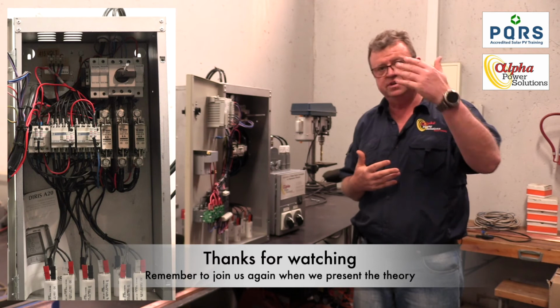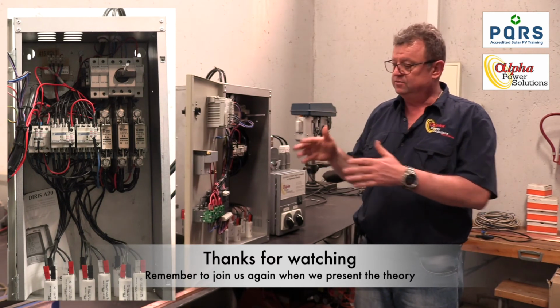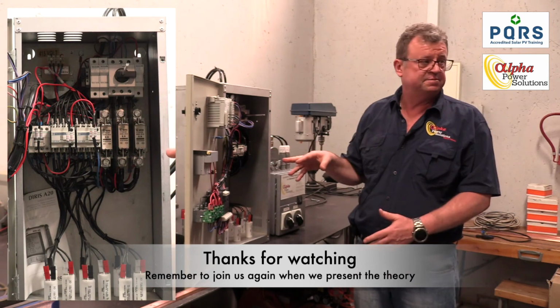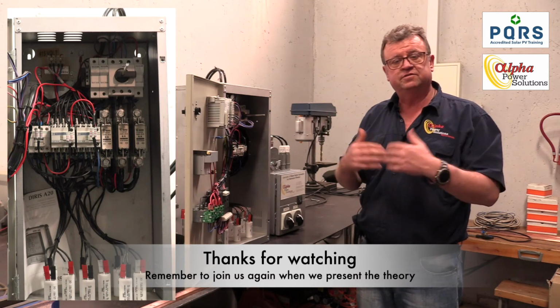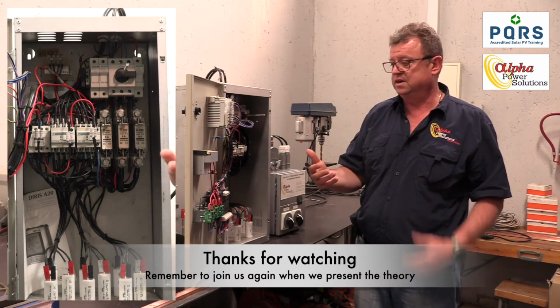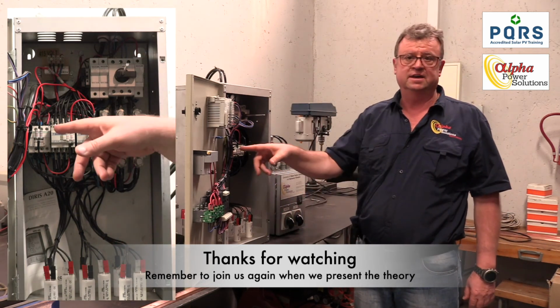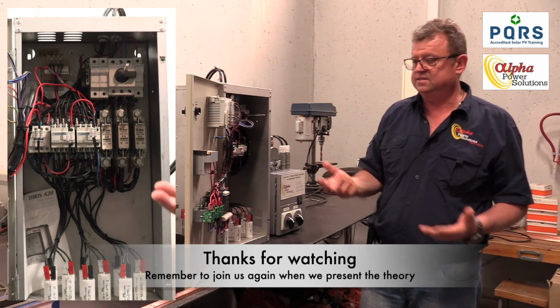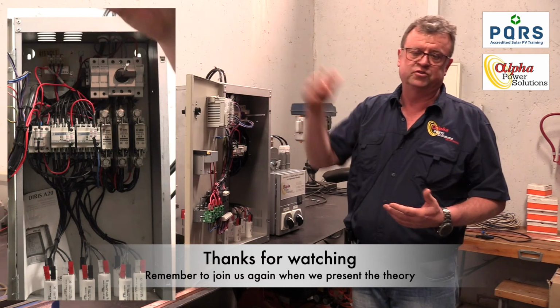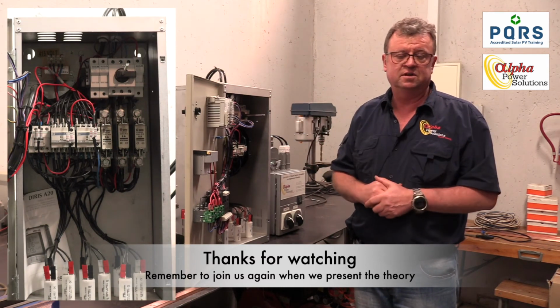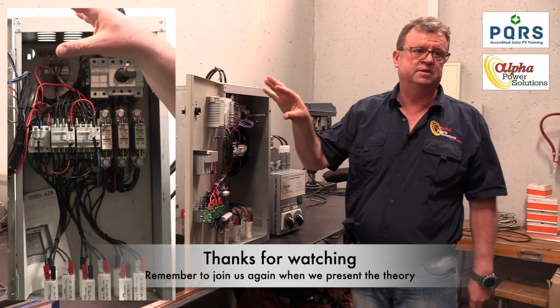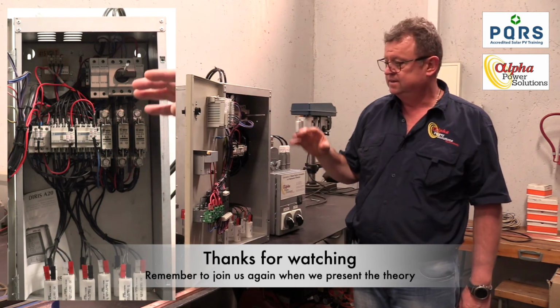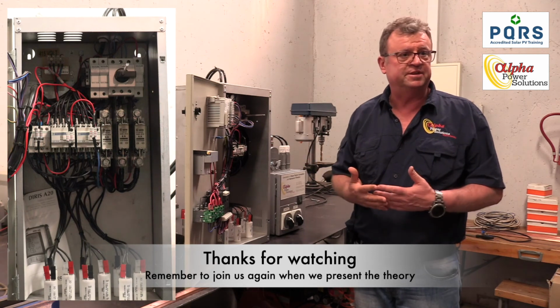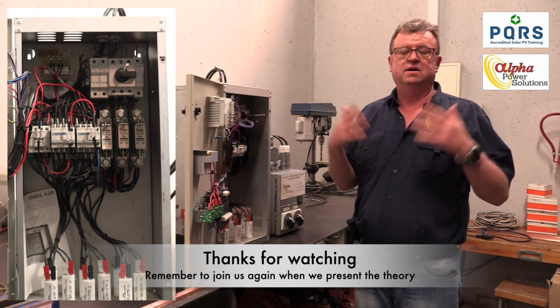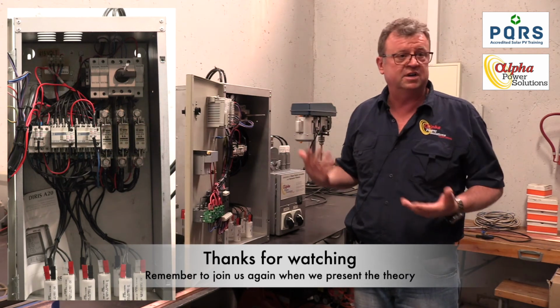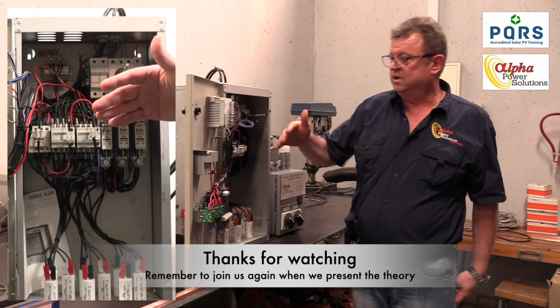When it knows it needs to increase the amount of reactive power it produces, it will select which of these, in this case 3 steps, to bring in. Similarly, if the load drops and less kilovars are required, the brain will decide which of these 3 it will kick out. So it's a completely automatic system. If the power comes up, this controller boots itself up, and after the programmed discharge time of the capacitors, a parameter that you set in the controller, it will start deciding whether it needs to do something or not. For example, if there was load shedding and the power is restored, but none of the motors are running in the factory, it will do nothing. And then as the load picks up, it will add.